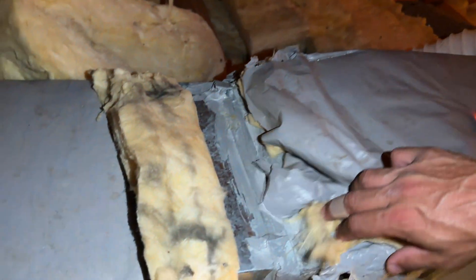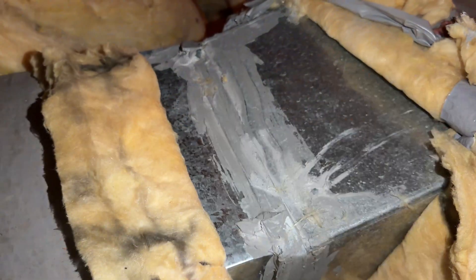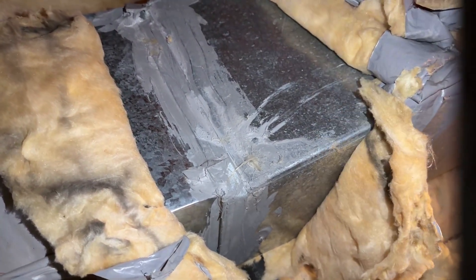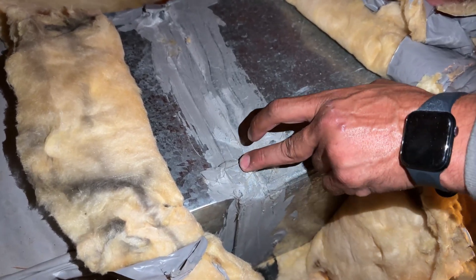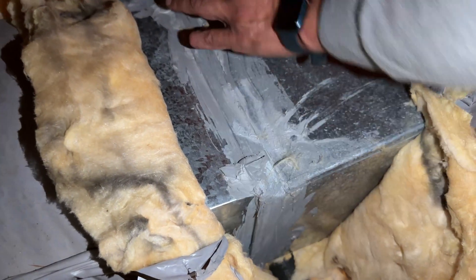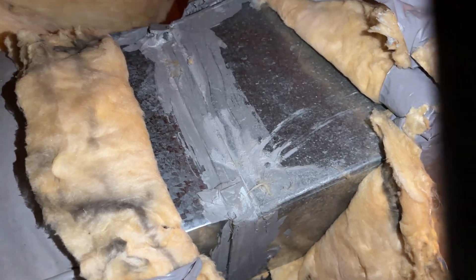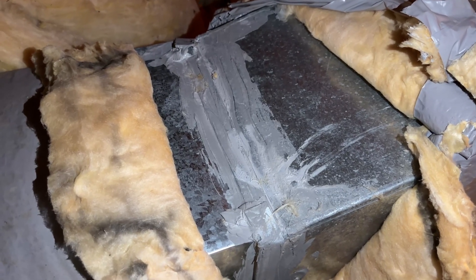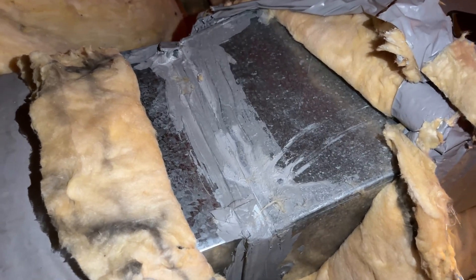There's ductwork up here in the attic. Part of the program standards is duct sealing — any seams, joints, bends where the tongue and groove meets, S-locks or S-bars where these lock in. You're supposed to hit all seams to make the system more efficient and help with heating and cooling costs. If a system has 50% leaks it's only 50% operational — sealing most of those leaks helps the homeowner and extends the life of the system.